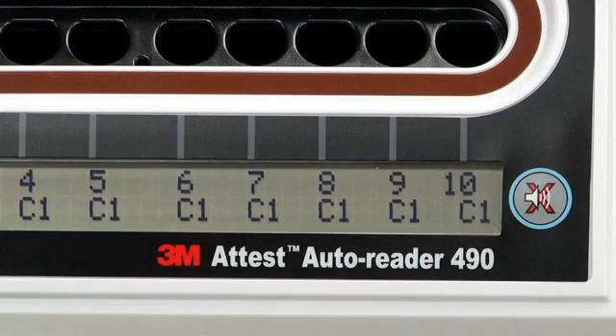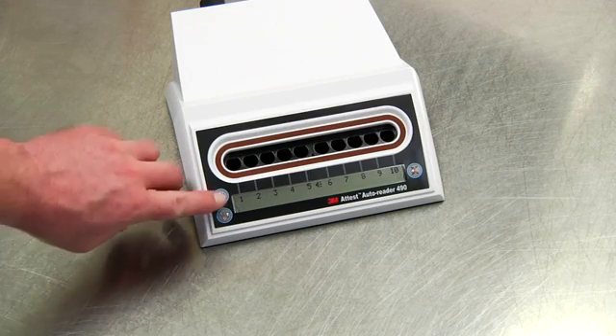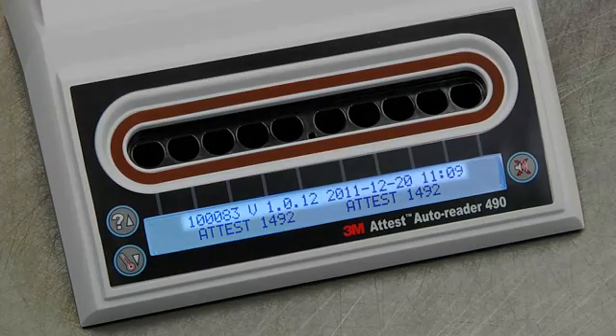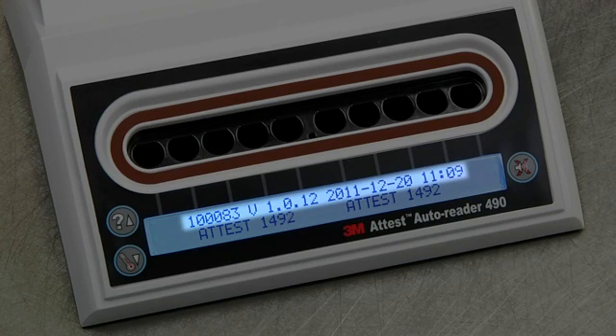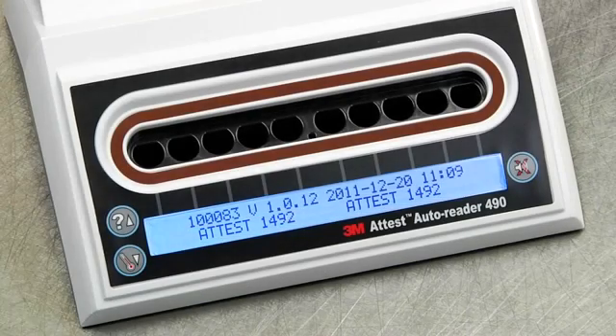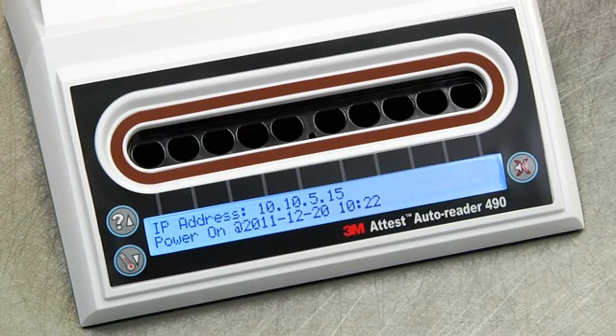When proper incubation temperature is reached and the Attest Auto-reader 490 is ready to use, the C1 caution code will disappear. When you press the Information button once, the LCD display gives the Attest Auto-reader 490 serial number, the version of the embedded software, and the current date and time. The bottom row shows the configuration for the BI incubation wells. Press the Information button twice to display the IP address if the unit is connected to an Ethernet jack, and the date and time that the Auto Reader 490 was last powered up.